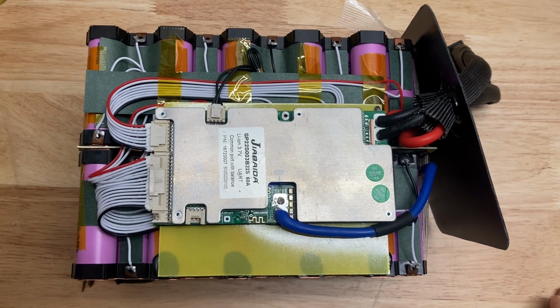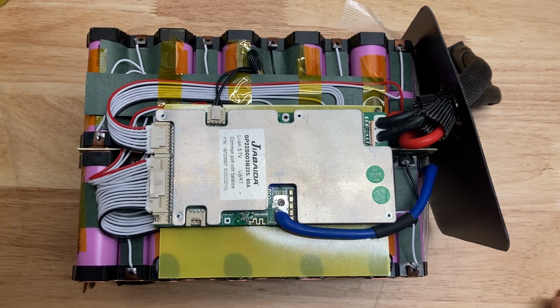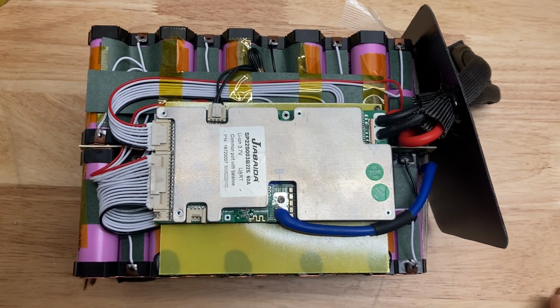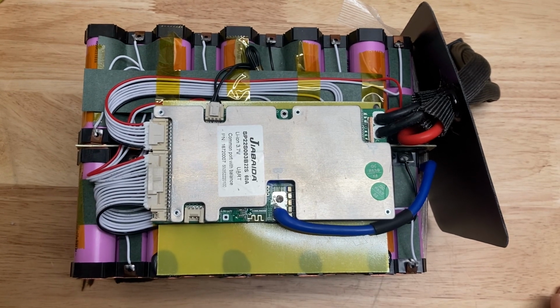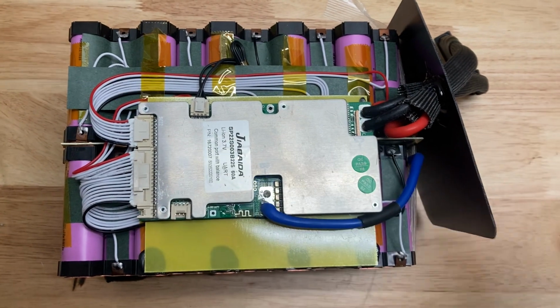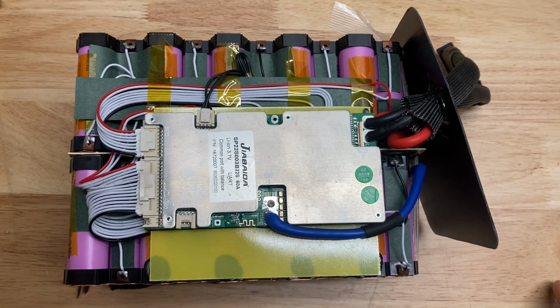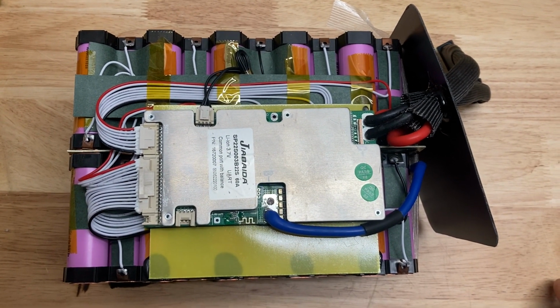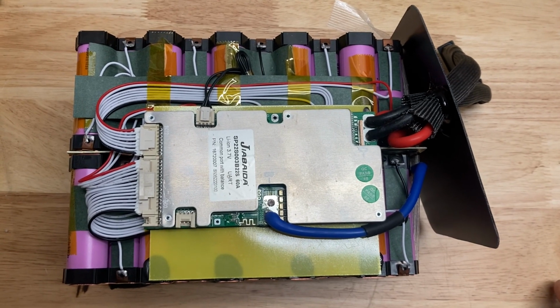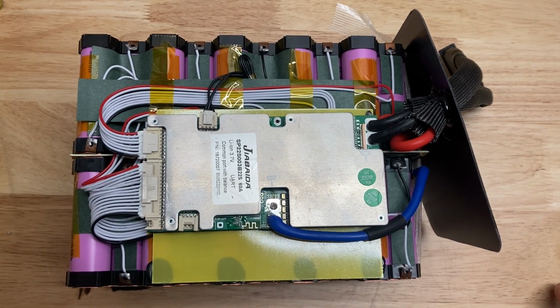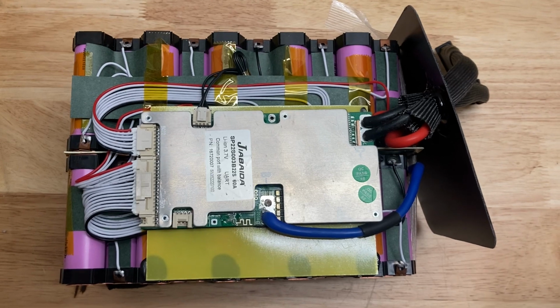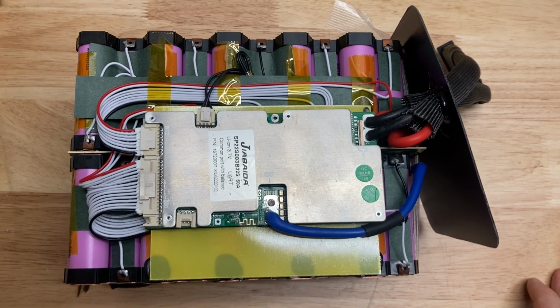If you make a mistake, you'll have to enter that manually. I've made a mistake wiring this before and had 7.2 volts between two adjacent balance leads, and I could see that on the app, so it was easy to locate. It did not damage the BMS, at least not for 7.2 volts. If it were a bigger mistake, like 10.8, maybe that would have caused a problem.